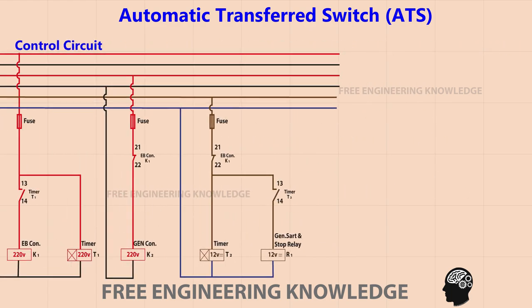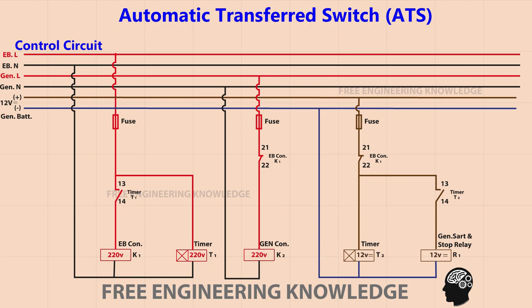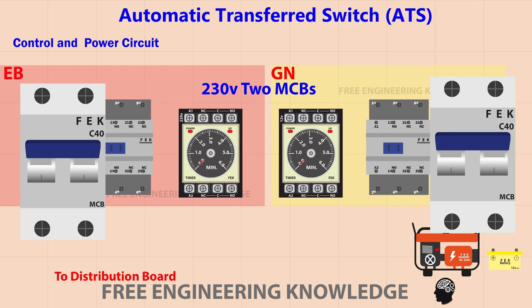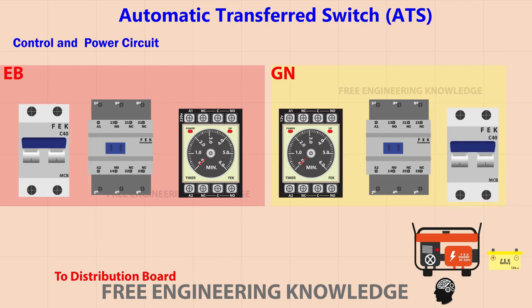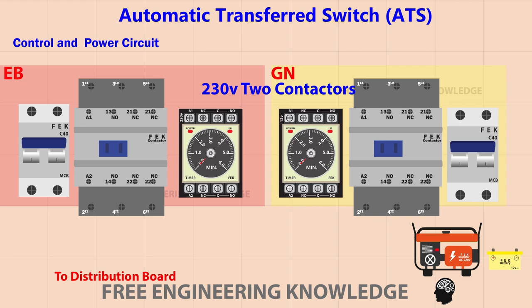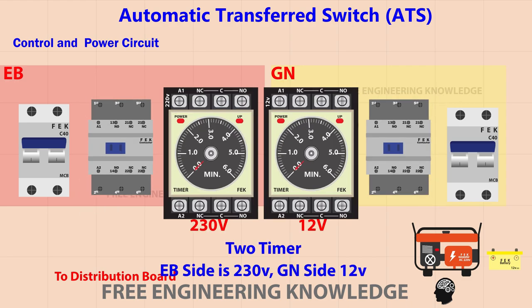Let's look at the control circuit diagram of the automatic transfer switch. Two timer relays are used in this — we'll see why in the next section. The necessary electrical equipment includes: two 230-volt MCBs (amperage adjustable to your usage), two 230-volt contactor relays, and two timer relays — one 230-volt for the EB side and one 12-volt for the generator side.